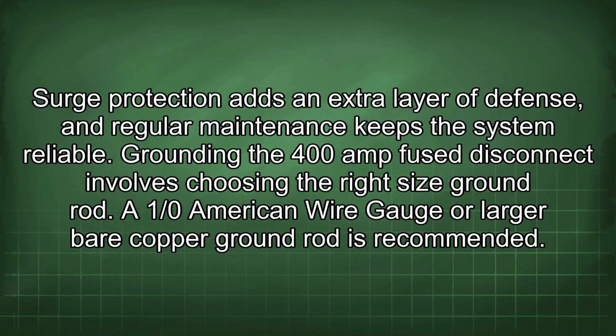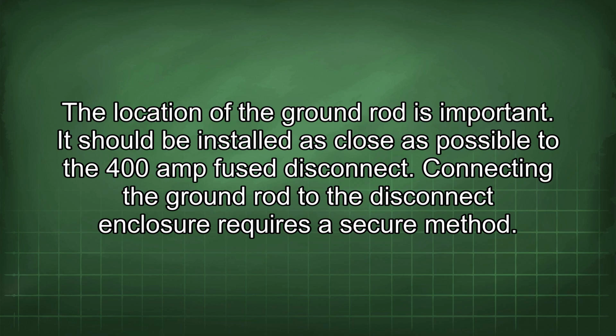Grounding the 400 amp fuse disconnect involves choosing the right size ground rod. A 1/0 American wire gauge or larger bare copper ground rod is recommended. The location of the ground rod is important. It should be installed as close as possible to the 400 amp fuse disconnect.